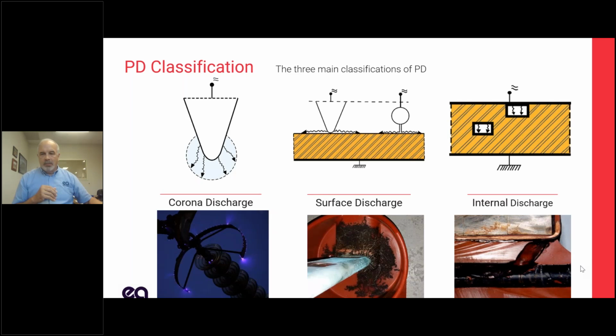We take partial discharge and we break it down into three basic classifications: corona, surface, and internal discharge. So corona discharge, and lots of people around the world use the term corona discharge and partial discharge interchangeably. Corona is actually a subset. It is one form of partial discharge. It is where the discharge, this current, is going directly from a conductor through a gaseous medium. 99.99% of the time, that's air. So when you discharge directly to the air, that's corona.